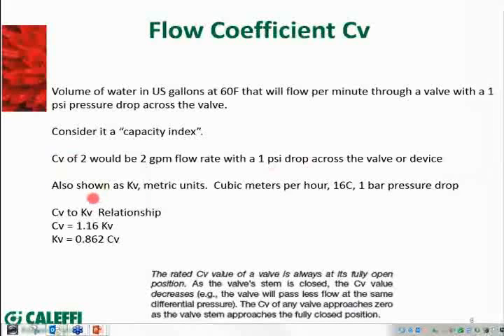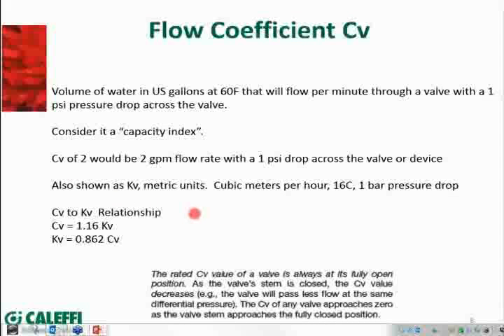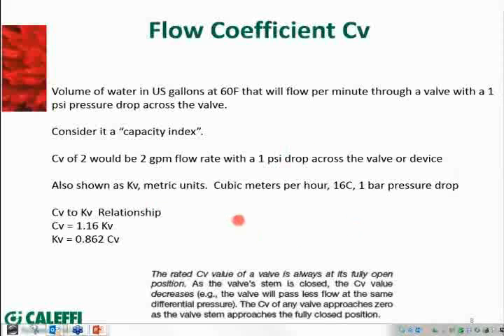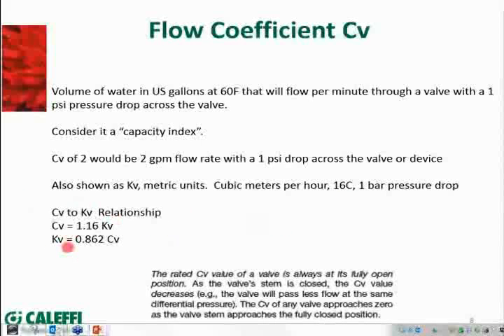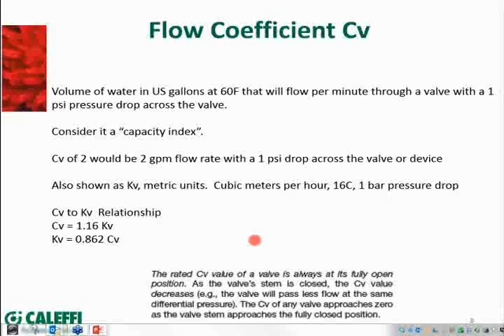You'll also see this expressed sometimes in metric units, especially with Caleffi components since we sell worldwide and most of the rest of the world works in metric. You'll see this expressed as KV — K sub V — which would be cubic meters per hour at a temperature of 16°C with a one bar pressure drop. Instead of using the English terms of GPM and PSI, we've put that in metric terms, and there are numbers to convert back and forth. What we try to do on all our products when we show data sheets is show both CV and KV, which makes it usable anywhere in the world.